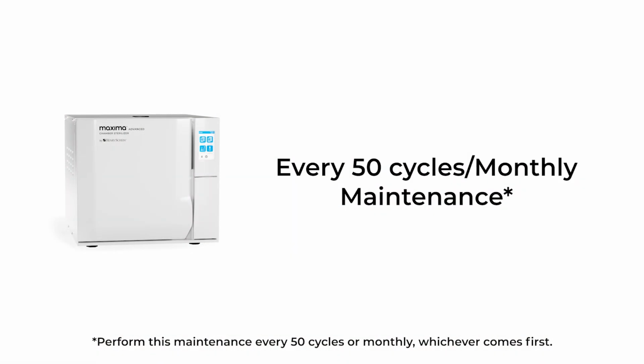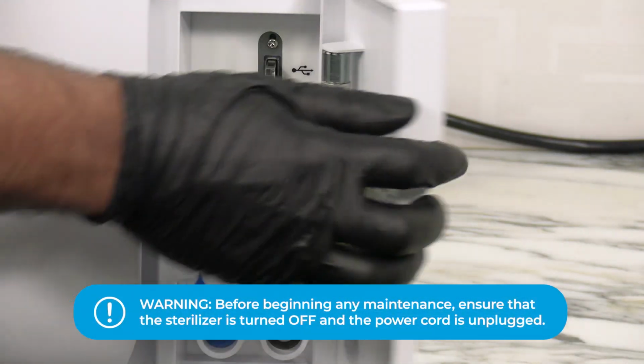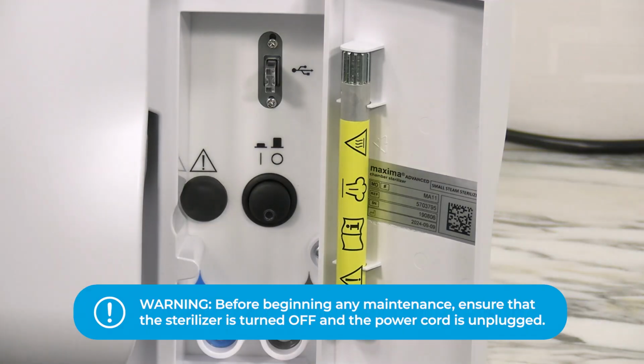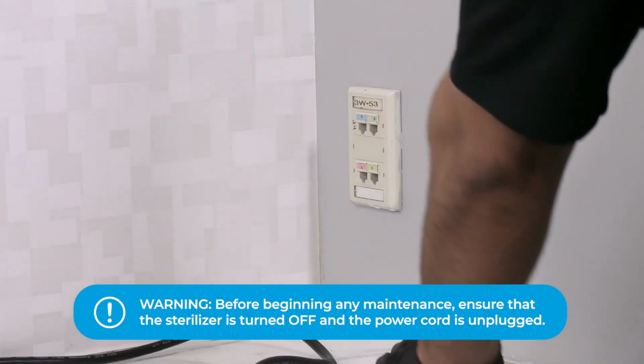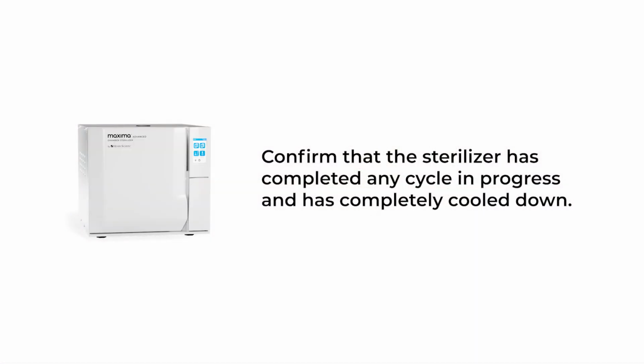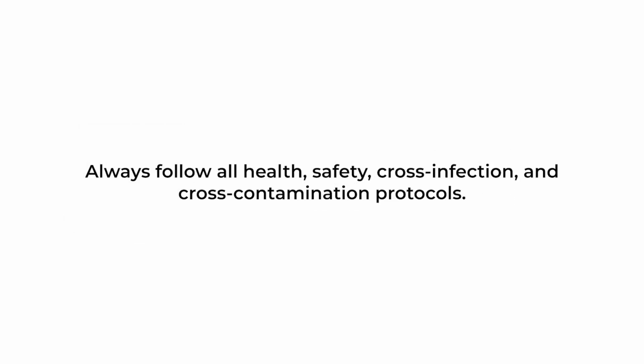Monthly or 50 cycles maintenance. Warning: before beginning any maintenance, ensure that the sterilizer is turned off and the power cord is unplugged. Also, confirm that the sterilizer has completed any cycle in progress and has completely cooled down. Always follow all health, safety, cross-infection, and cross-contamination protocols.